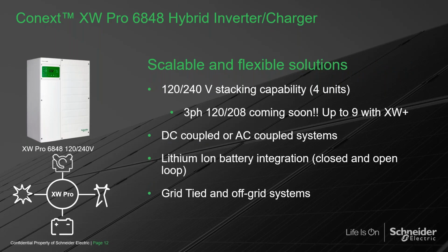Scalable and flexible solutions. So the XW Pro out of the box is a 120/240 volt solution, so you don't need an external transformer to get 120/240 output. We can stack 4 units in parallel in that configuration. Later this year, we're going to have 3-phase capability, which is 120/208. So you convert the units to 120 volts, put 1 inverter per phase, or if it's up to 9 inverters, that would be 3 inverters per leg. DC coupled or AC coupled systems, as we talked about, lithium ion batteries for closed and open loop. And finally, this is for grid tie and off-grid systems. Next slide.